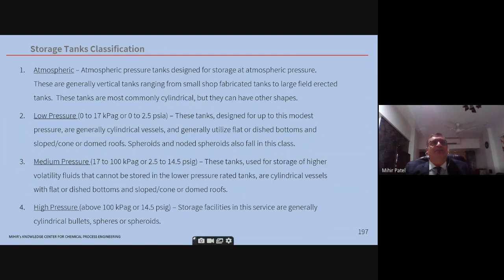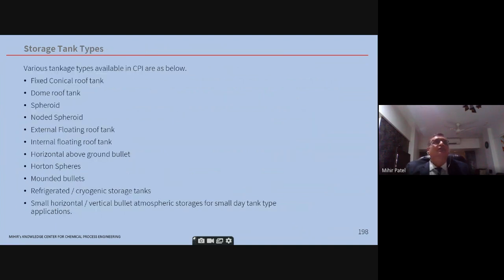which come into the spheres and cylindrical bullets. For example, as I mentioned, LPG is stored in cylindrical bullets. If it is propane, you have a design pressure of 21 bars. If it is butane, you may have a design pressure of around 15-16 bars. So these are the high pressure category vessels. Storage tank types, now this is important.